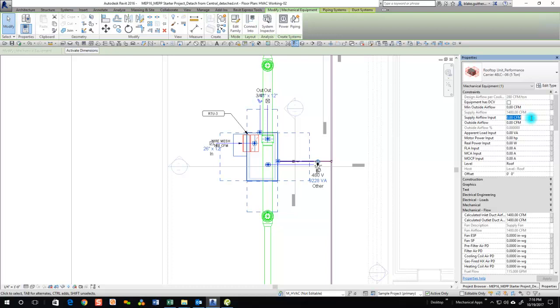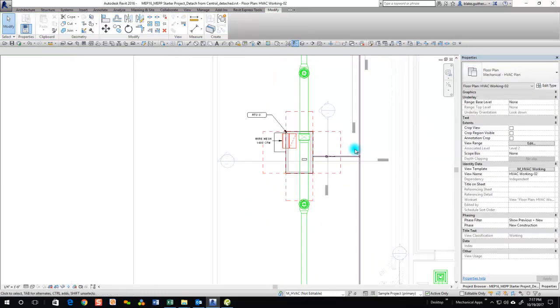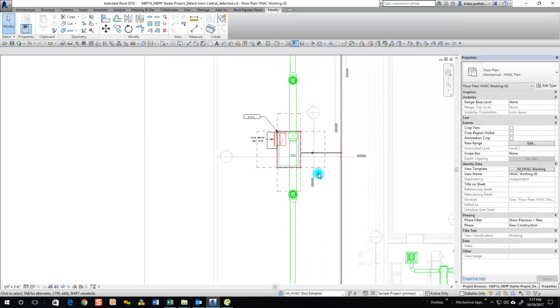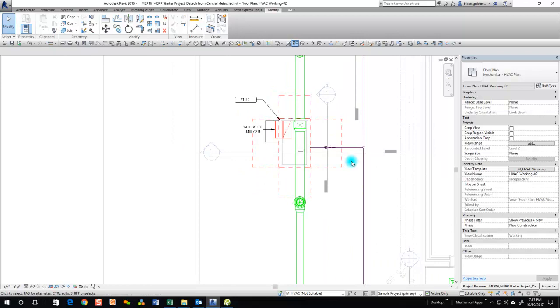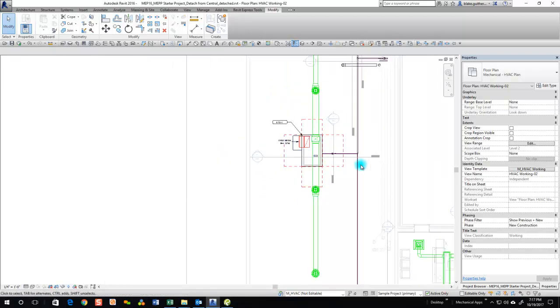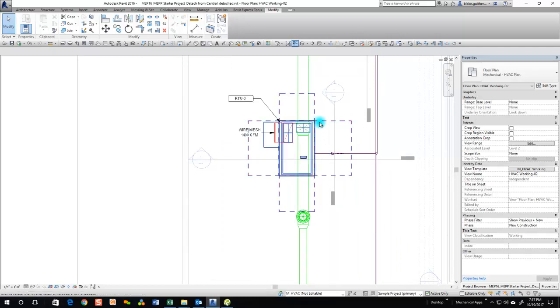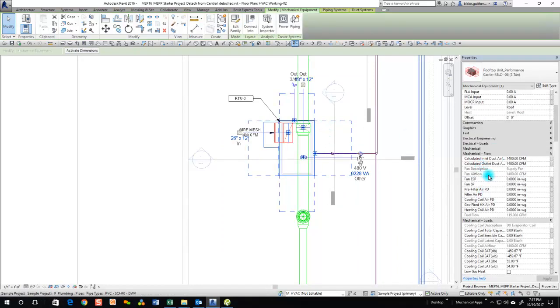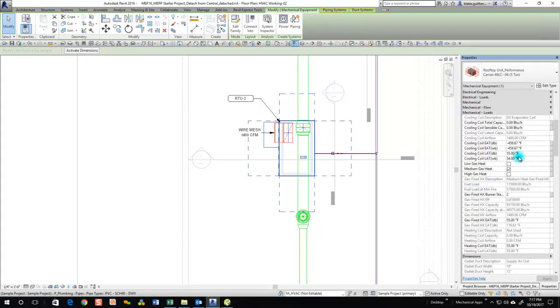So let's say we wanted 300 CFM per ton. We could say equals 300 times 5 for a 5-ton unit. So we can update things that way. I'm going to keep the override at 0 for now. The outside airflow, well, we'll edit that later because I want to show you guys how to work this family and the schedules. So there we go. Family's placed, everything's connected, electrical has loads, everything has airflow, the gas system has a load. Let's look at some of the calculations now for the gas-fired heat exchanger. So cooling coils, we're not doing any calculations yet.